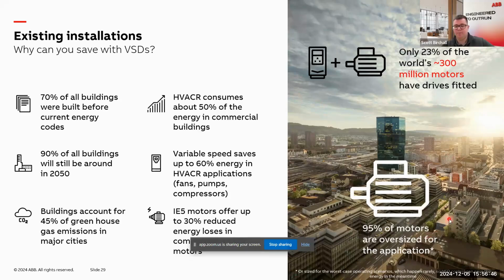95% of motors are oversized for the application. Tim touched upon this with the sizing for worst case. I mean, we said 95%, which is probably more - I can't see many actual applications where you can size absolutely bang on for the application. It's very difficult. So most motors need to be controlled in some way. That's something that's got to be considered.